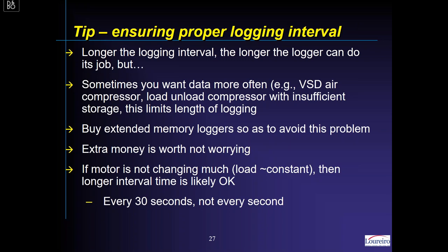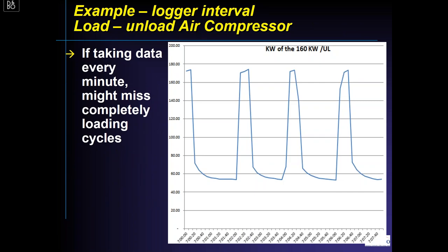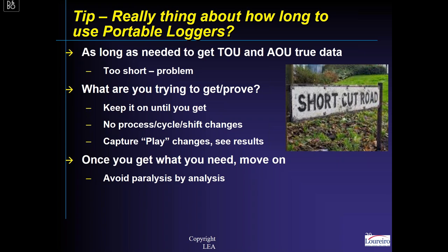If the load changes a lot, capturing cycling matters. This could be an air compressor, reciprocating chillers that stage on, or HVAC equipment. If you're taking data every minute, you would not see the loading cycles where the average goes up to well over 160 amps for a short period before the compressor unloads and runs at about 60 amps. If you took data every minute or every five minutes you would miss all these changes. You need to know that.